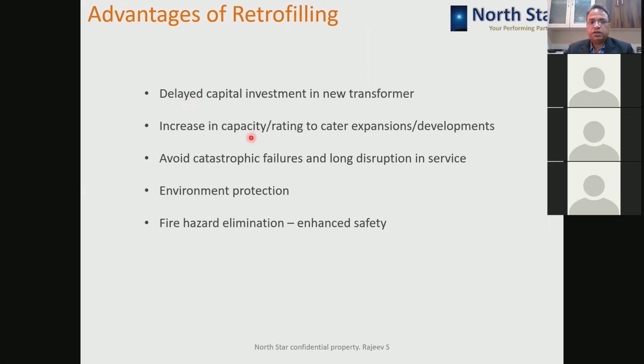Then increasing capacity and rating: if your load is increasing or you are going to expand your facility, then you don't have to replace the transformer, you just replace the liquid insulation with natural or synthetic ester, and you can cater to an increasing load of up to 10 or 15%, 20%. Okay, then you avoid catastrophic failures and long disruption in service. You are protecting the environment, and you are enhancing the safety of your own people and your own property by going for natural and synthetic esters.